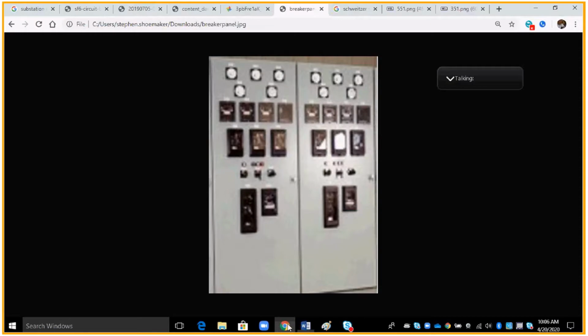Right, back to our photograph right here. Phase A, B, C, they send a signal to the breaker to open. Ground can also send a signal to the breaker to open. Reclosing relay right here, that one recloses the breaker back.